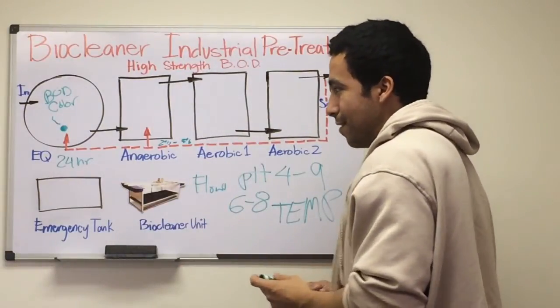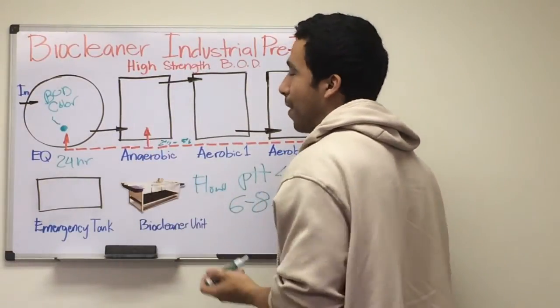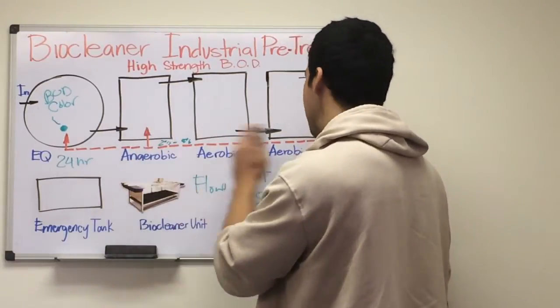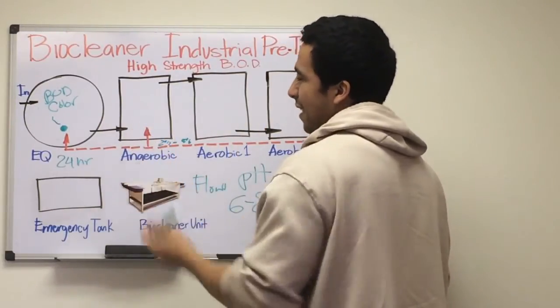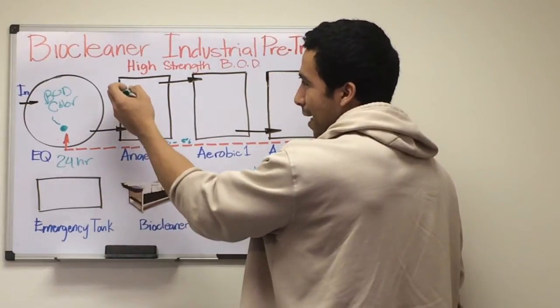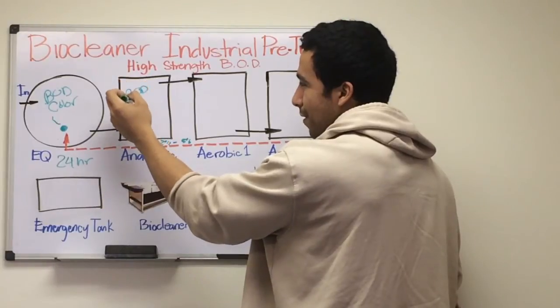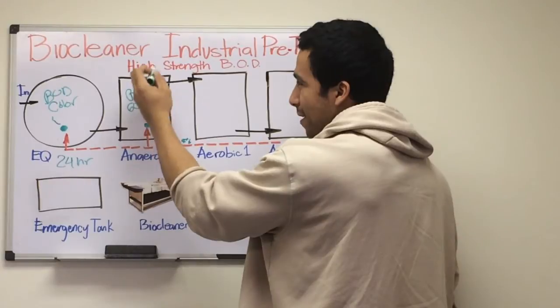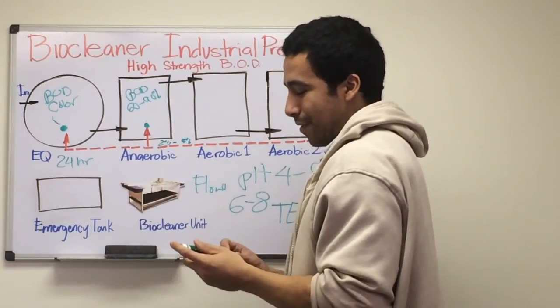After equalization, our first process in secondary treatment is anaerobic. We dose microbes here, and this is where we have most of our BOD reduction, from anywhere from 60% to 90% depending on the contaminant strength.